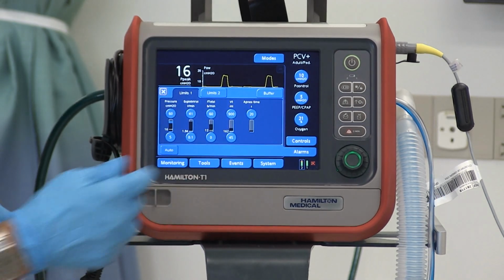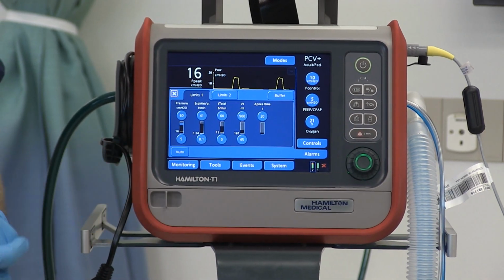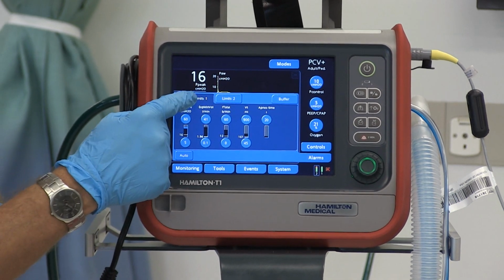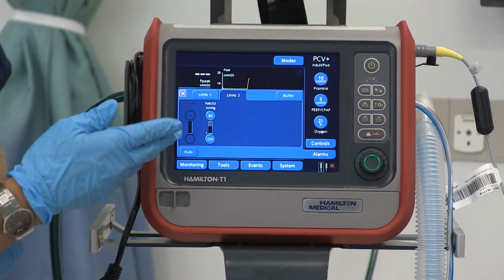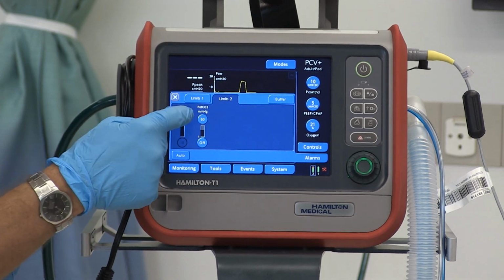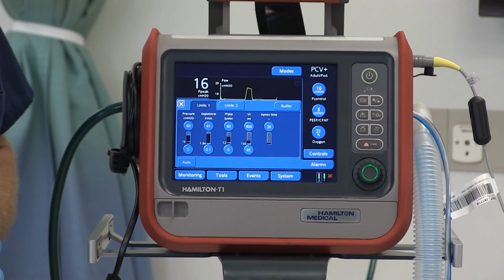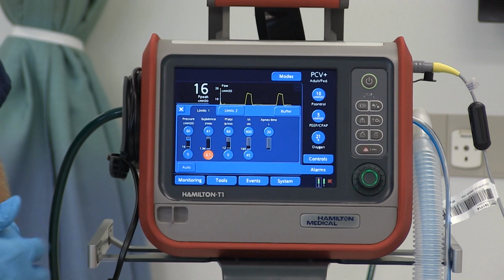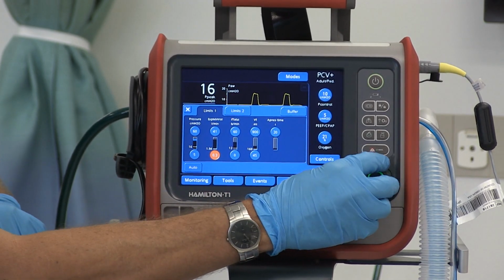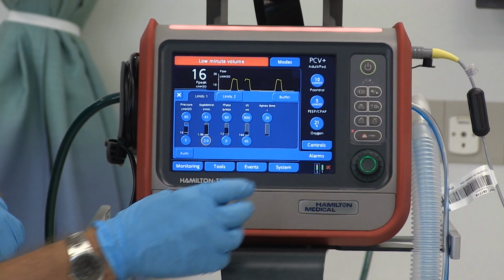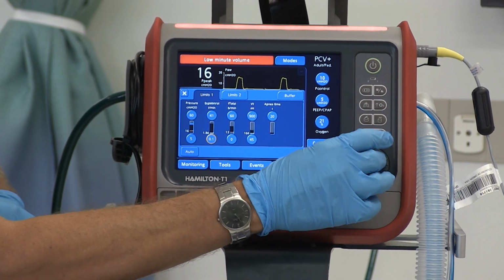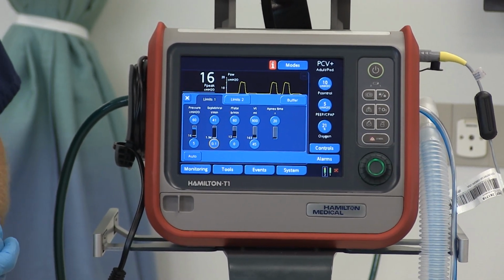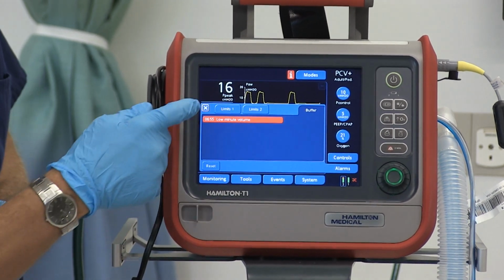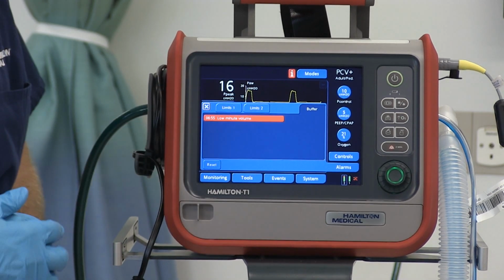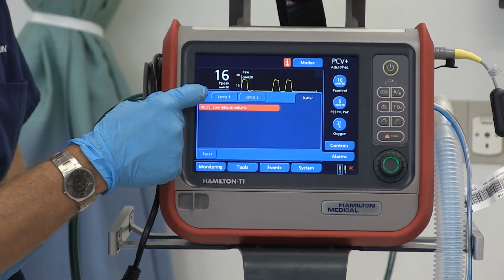The tab below that is the Alarms tab. Here we find all the alarms. There's two sections, limits number 1, limits number 2. Number 2 is where you'll find your end-tidal CO2 alarm and your SpO2 alarm. To adjust the alarms, activate, in this case, the lower alarm setting, adjust, and confirm. Here on the right side of the alarms window is the buffer window. This is the same window we saw when we hit the red information tab, and it shows our recent alarms.